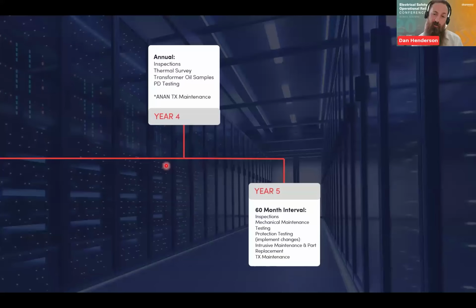And then the 5-yearly maintenance, which we'll cover a bit more in depth, we're going to be shutting it down. It's going to be intrusive. So we're going to be doing all the mechanical maintenance, the electrical testing, protection testing. If we've had any protection studies done, so fault level assessments, grading studies, or arc flash surveys, and we need to implement any changes into the relays, again, this is the time to do it. Because we've got the network off, we can change the settings in the relays, and then we can do the trip time testing of the breakers to those settings to make sure that it actually works. So it's good to try and correlate your activities around your maintenance program to get the best use of your outages and your downtime. If there's any changes that you need to make or parts replacement, you can do it then.